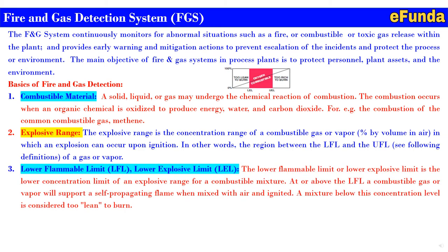Third, lower flammable limit, that is LFL, or lower explosive limit, that is LEL. The lower flammable limit or lower explosive limit is the lower concentration limit of an explosive range for a combustible mixture. At or above LFL, a combustible gas or vapor will support a self-propagating flame when mixed with air and ignited. A mixture below this concentration level is considered too lean to burn. One can correlate with the figure above.